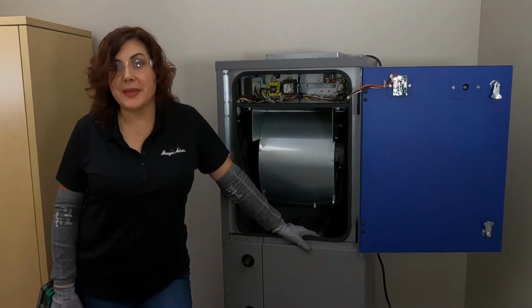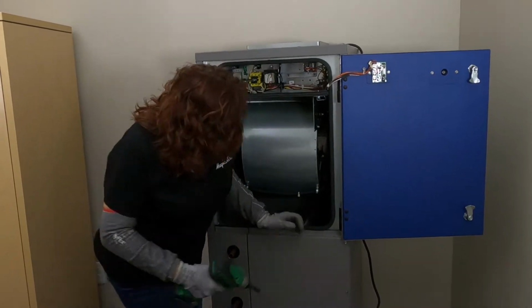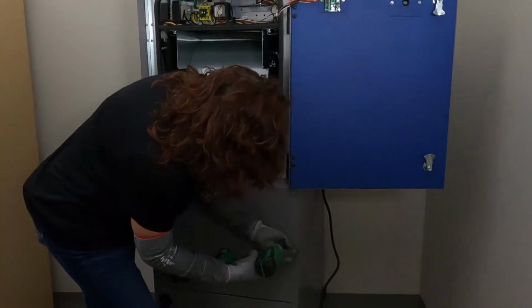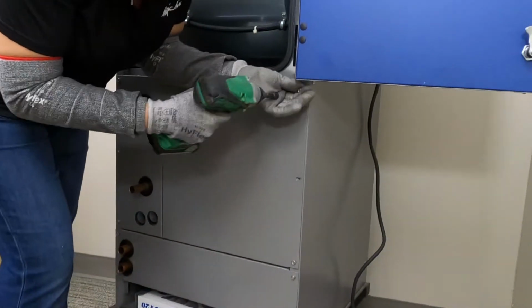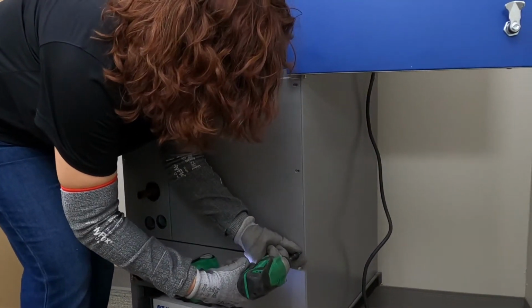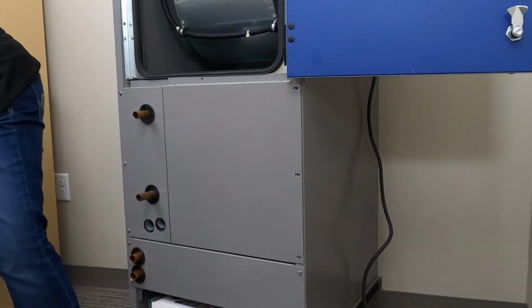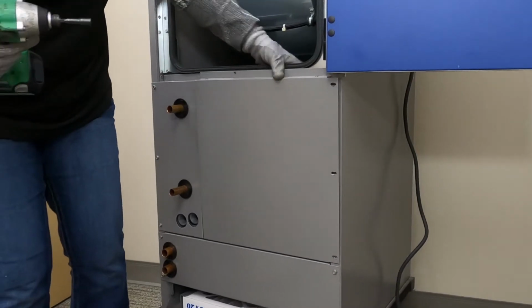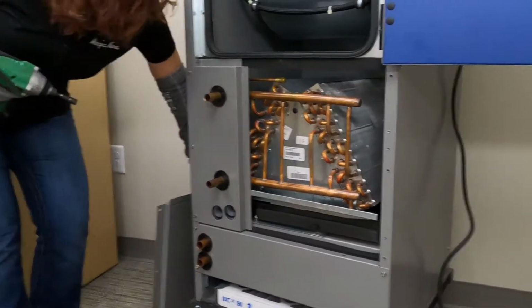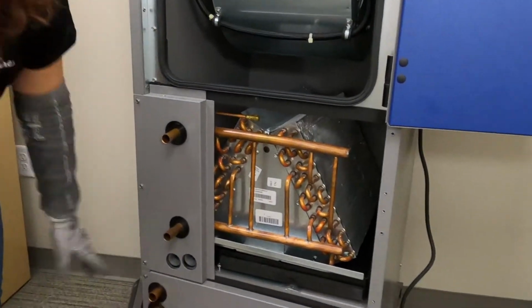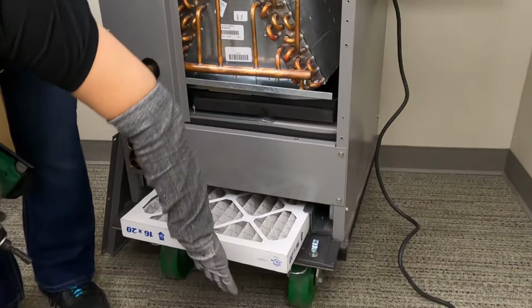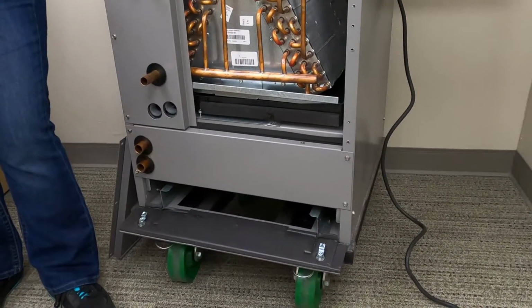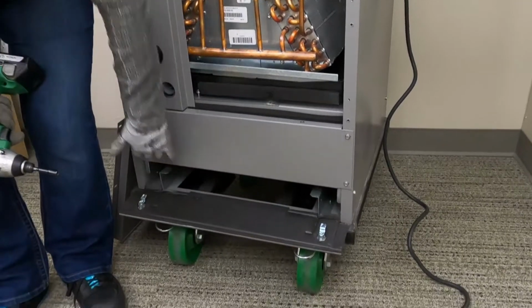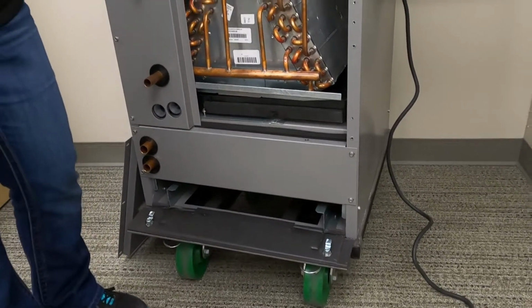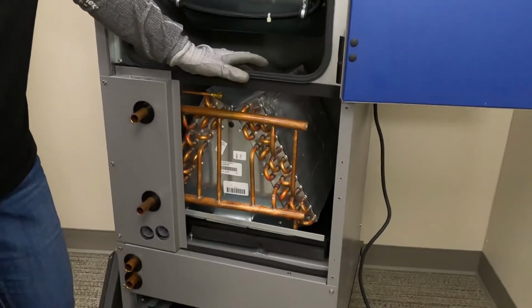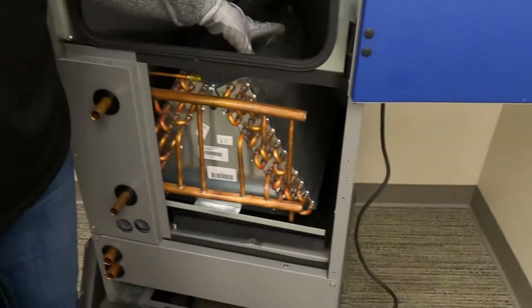The next item on our preventive maintenance list is servicing the coil. To service the cooling coil, you're going to have to remove the right exterior panel. Make sure you don't lose any screws. This pops off fairly easily and removes. To do this well, you're going to have to remove the filter, and you're going to want to put a pan here to catch all of the liquid. So you're going to use whichever cleaning solution your HVAC distributor recommends. It has to be non-acidic.